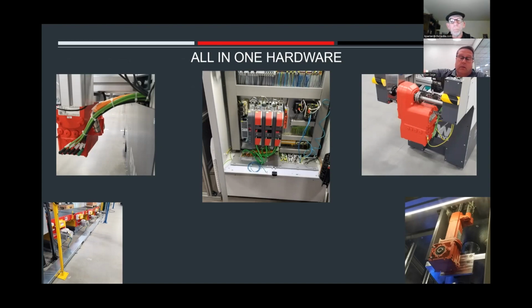And I know at 1 o'clock in the morning, when the individual is concerned about getting the machine up and going, sometimes as much as you'd like them to be, they're not necessarily concerned about whether they have time to get their proper PPE on. It's not an excuse. It's not acceptable, but it happens. You get in a hurry trying to get that machine up and going, and you may risk some things getting into that enclosure, if they're even allowed in. Maybe they're not even certified, so the machine then sits down till the morning when someone can. And a lot of times in a decentralized application, you can disconnect power remotely to that one piece, reconnect or replace the right unit, retie your cables in, turn your power on, it reads, it's configured, and you are up and going.